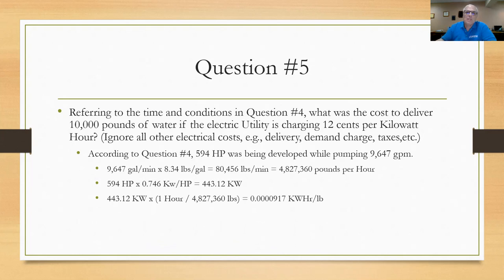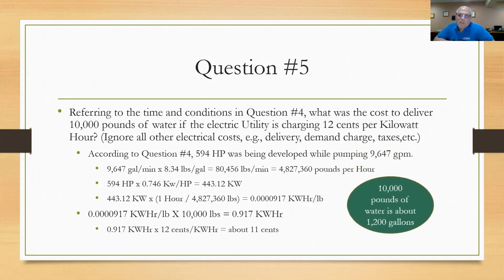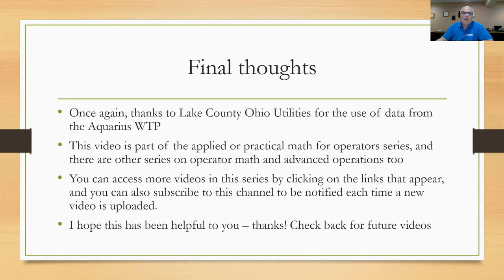Very small amount, I'd say. But let's see what it takes for 10,000 pounds. You take that kilowatt hour per pound of 0.0000917, multiplied by the 10,000 pounds, I come up with 0.917 kilowatt hours being used. Well, 0.917 kilowatt hours times 12 cents per kilowatt hour is about 11 cents. Not bad. 11 cents of electricity to move 10,000 pounds of water. By the way, if you're interested, 10,000 pounds of water is about 1,200 gallons of water. Obviously, your charges for electricity is not a lot right there.